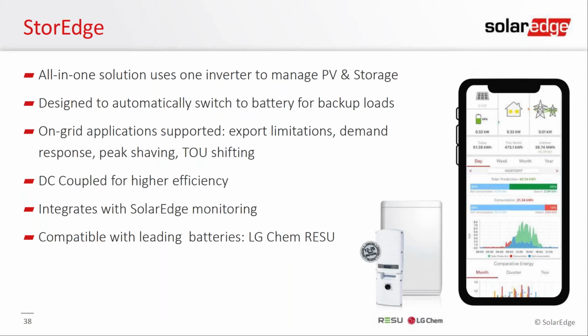We won't go into too much detail on that, but we're taking the PV directly from the rooftop, DC direct current. We're putting that in the battery, which is also DC direct current. We're not switching it to AC and then switching it back to DC. We don't have to do any of those switching steps. So we're going to be getting that DC right into the battery.